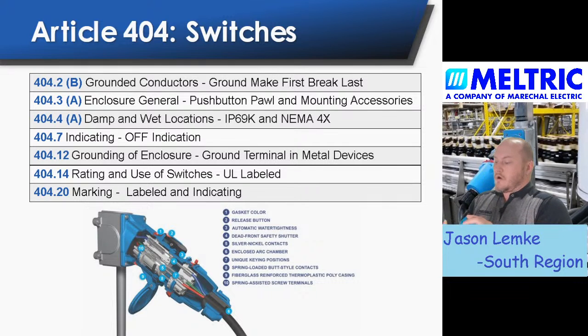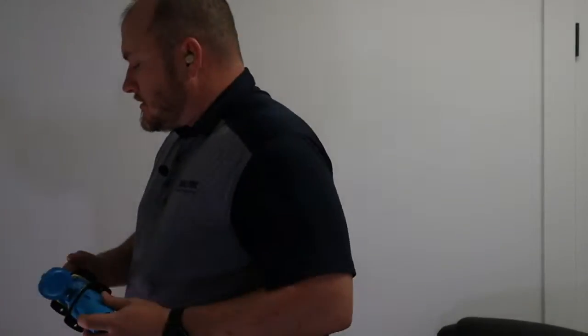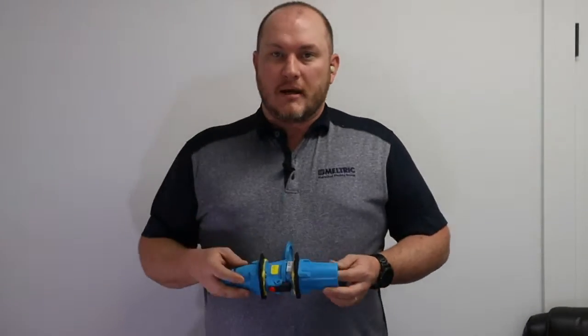So all of these requirements in NEC that you need to meet in order to be a switch, our device has been able to meet those requirements, giving us the ability to be an Article 404 switch in UL or in NEC, and actually allows us to meet UL requirements for a switch. So that kind of is the difference between a switch rated device and, say, a standard plug and receptacle.